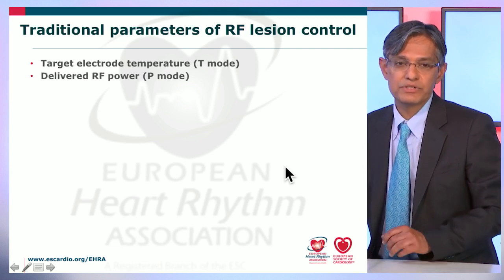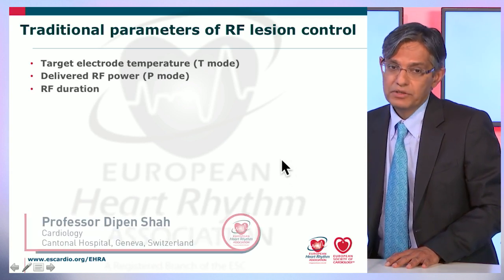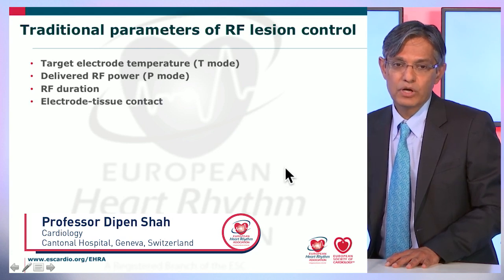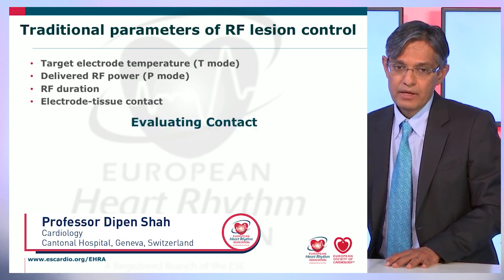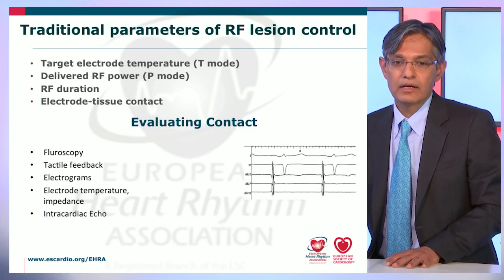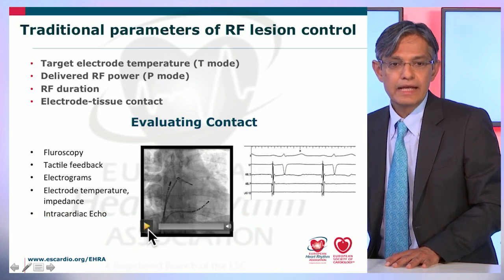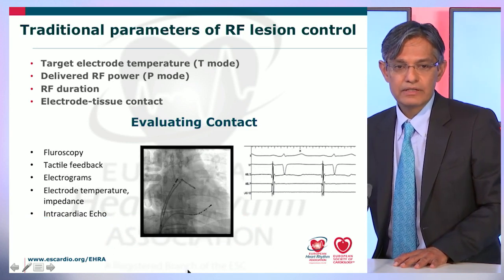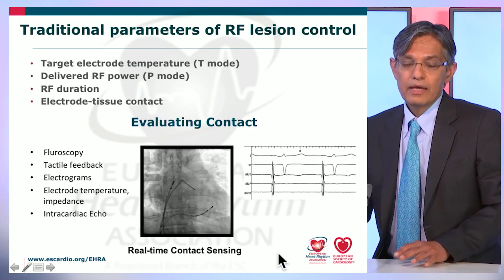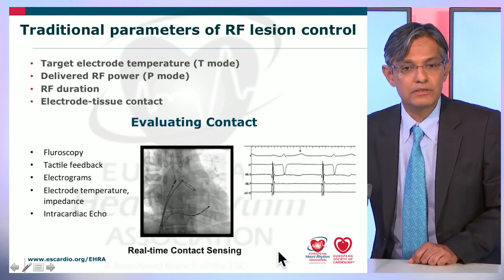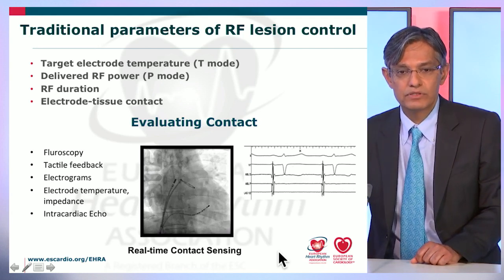You are all, or many of you are aware of the traditional parameters of lesion control for radiofrequency catheter ablation: target electrode temperature in temperature mode, delivered radiofrequency power for power mode, duration of RF delivery, and electrode tissue contact, which is very important and has been, till recently, very difficult to quantitate. Contact evaluation has been more an art than a science, incorporating fluoroscopy, tactile feedback, electrograms, electrode temperature, impedance, and in some cases intracardiac echo-based visualization. The availability of real-time contact sensing has allowed us to gain a new and valuable parameter of controlling lesion size.